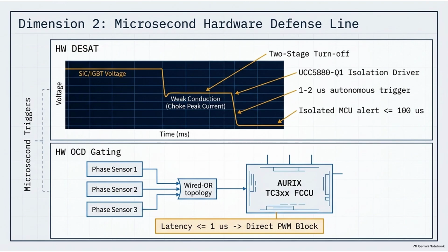Right. The two-stage turnoff navigates this perfectly. In the first microsecond, it drops the gate voltage to an intermediate level. It doesn't shut the door, it just pinches the hose. Right. This limits the maximum amplitude of the fault current, preventing the immediate melt. Then, in the second stage, it fully shuts off at a controlled rate, spreading out the di/dt so the resulting voltage spike stays below the avalanche threshold. That is an incredibly delicate electromagnetic balancing act, and it's handled autonomously in 2 millionths of a second.